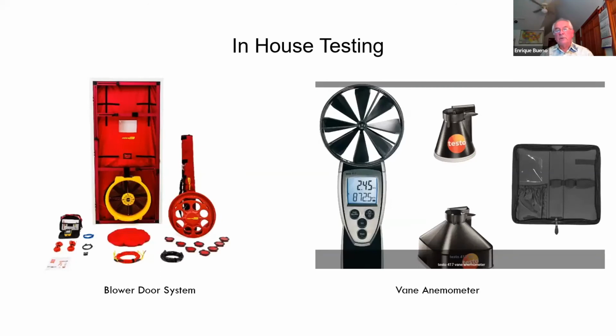In-house testing, we're going to be doing it in-house because there are no available services there. As a matter of fact, in Colombia, you can obtain a LEED Gold certification without having to perform a blower door test. Those are the conditions. So we purchased a blower door test system, as well as a vane anemometer to balance the ventilation air.